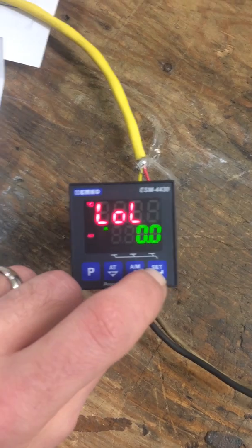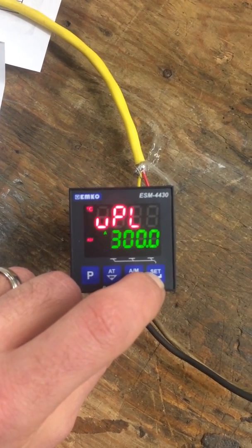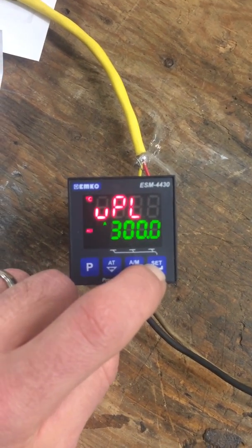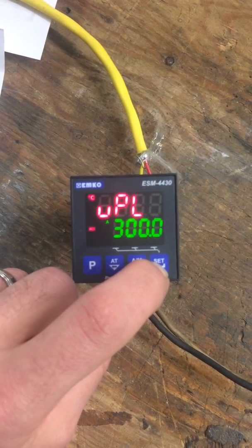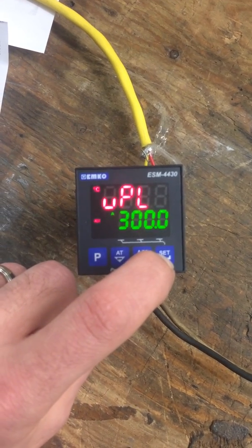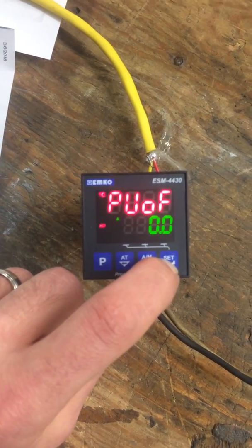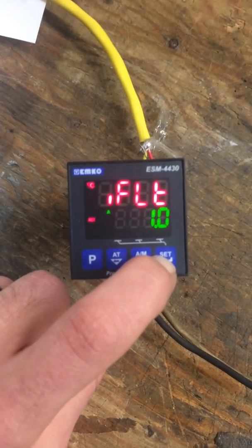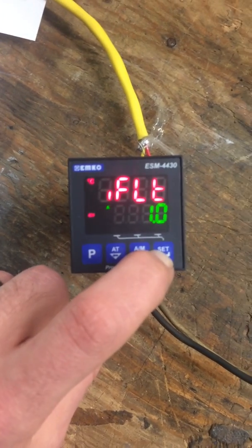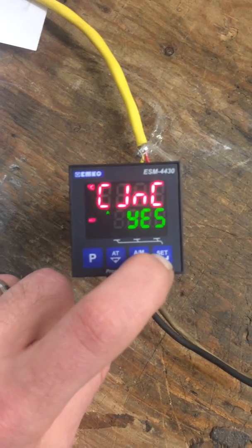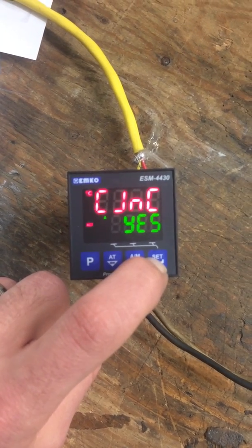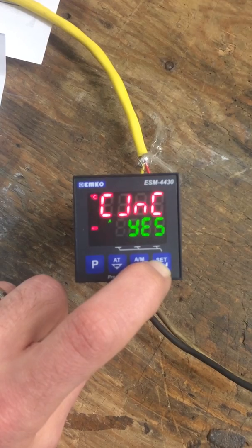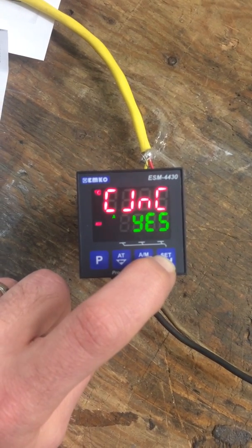In units, Celsius. Lower limit is 0, upper limit 300 — that allows us to essentially have a maximum range of 0 to 300 based on what the operation is. The process offset, we don't need to adjust this. The input filter time is one second. This is cold junction compensation — we want to have this on yes; it essentially compensates for the metal being cold.